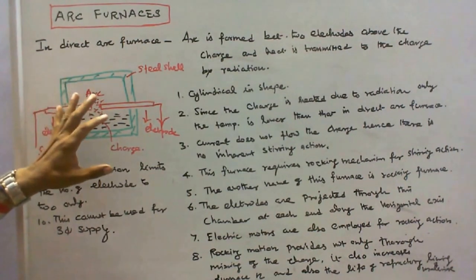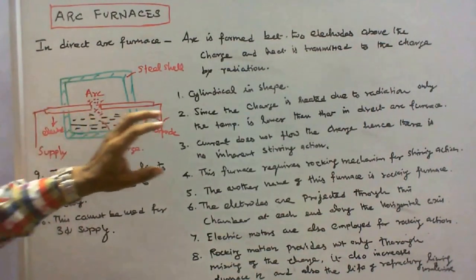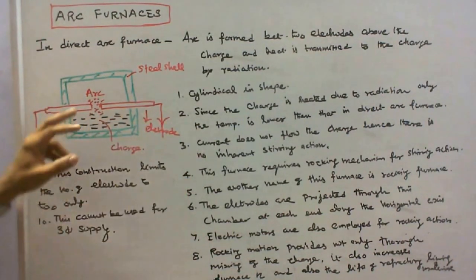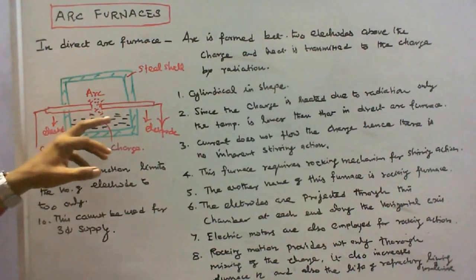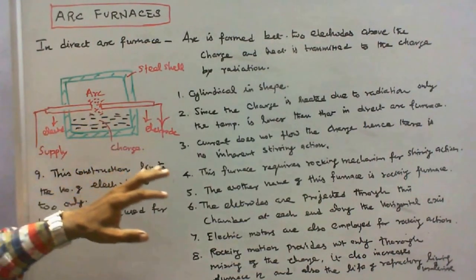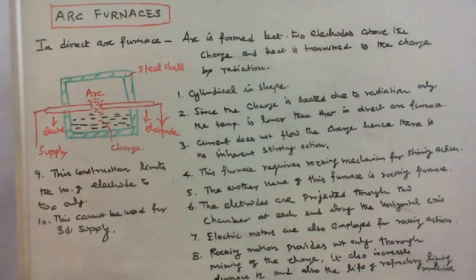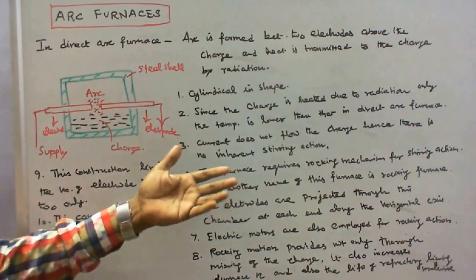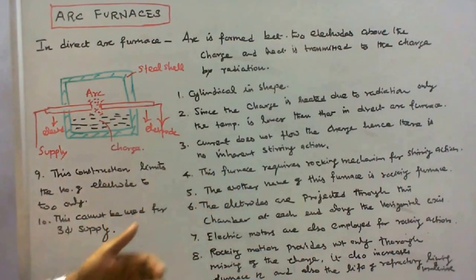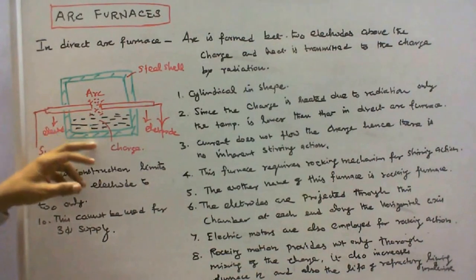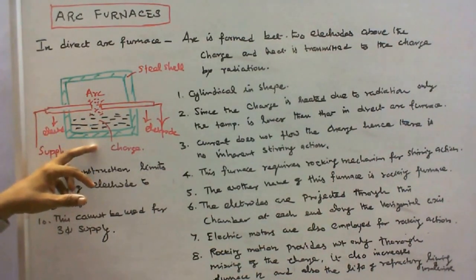Since the charge is heated due to radiation only, therefore the temperature is lower than that in direct arc furnace. Current does not flow through the charge, hence there is no inherent stirring action. The furnace requires rocking mechanism for stirring action. The another name of this furnace is rocking furnace.